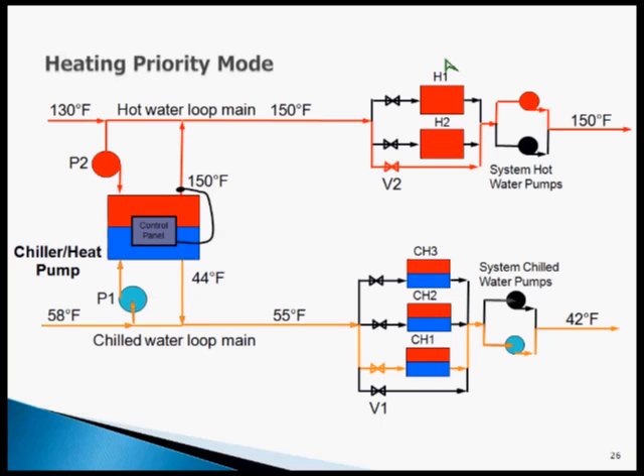So where we see these machines is in places that have reheat. Reheat is the bane of all energy engineers. We hate that. I mean, why are you making reheat in the summertime? That's crazy. Well, there's no other way to control humidity, and we're not going to put in desiccant, low humidity systems, because it's only 45 to 55 percent that we want to maintain. Oh, it's painful drawing the reheat systems on paper when you're an engineer, because think about the simultaneous heating and cooling.